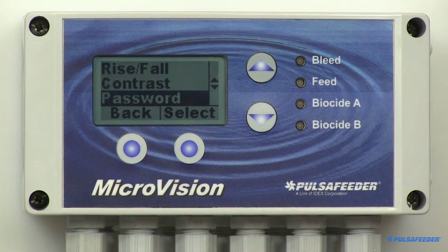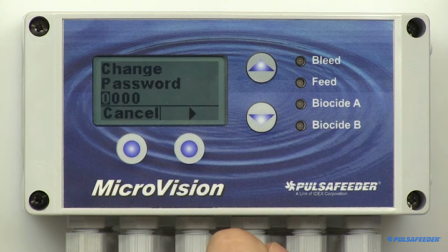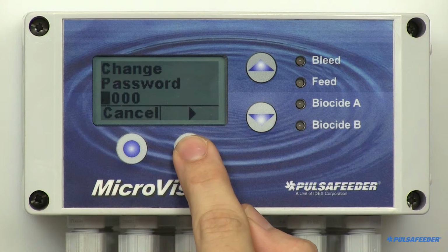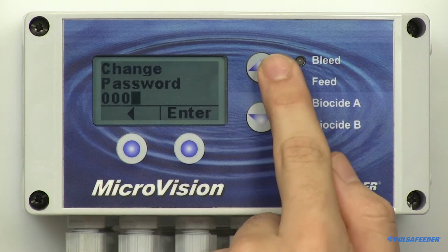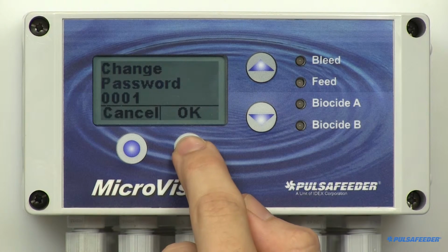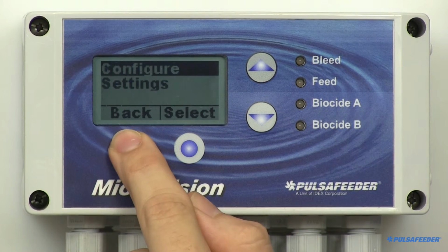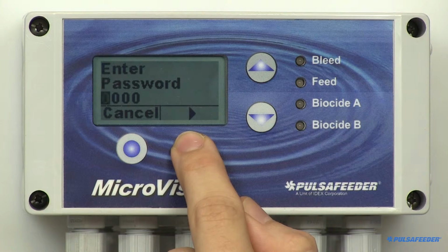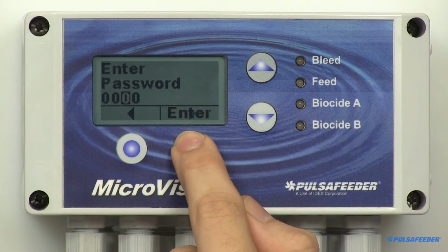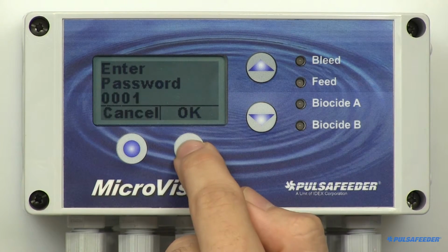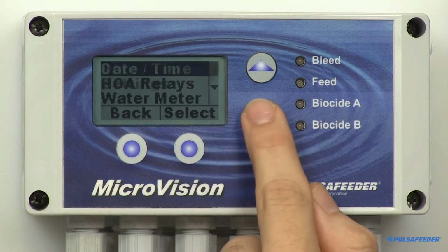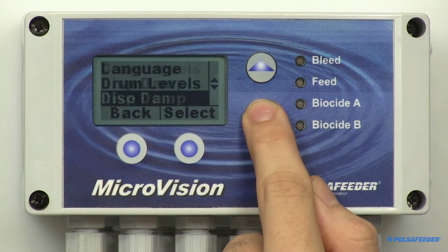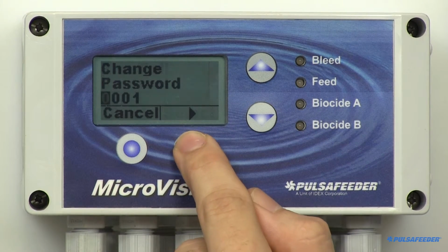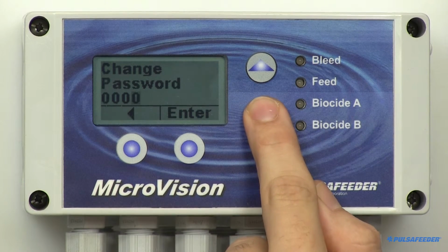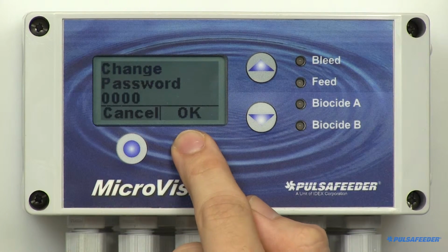The MicroVision can be password protected. This feature is found in the Configure menu. Scroll down to password and select it. You'll see that zeros are normally displayed. Setting this to anything other than four zeros will enable the password protection. The code will be required to access the Configure and Settings menu. To disable the password, return the code to zeros. If you do not know the password, you'll have to call our technical department for help. Please have the controller in front of you when you call.